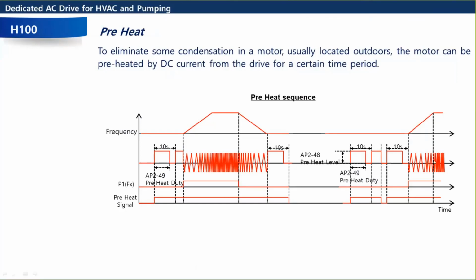Okay, so this looks like a complicated table here, but really all you're doing is flipping on a signal, which is your preheat signal. There's a delay time, and then this scribbly sawtooth waveform right here, that would be your motor preheat. Okay. Actually, sorry, this is your regular operation here. That's trying to show our PWM. The motor preheat would just be a solid signal, like these squares. And then you could set a preheat duty cycle so it goes on and off. And then there's a current level that typically you'd want pretty low because you are injecting DC into the motor.